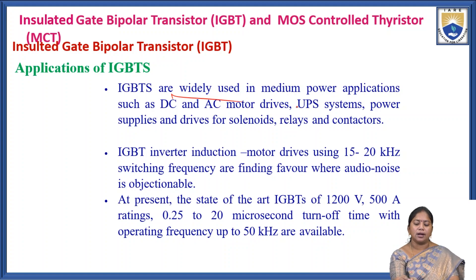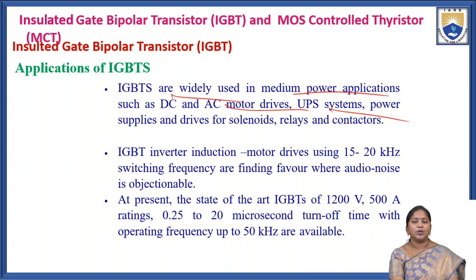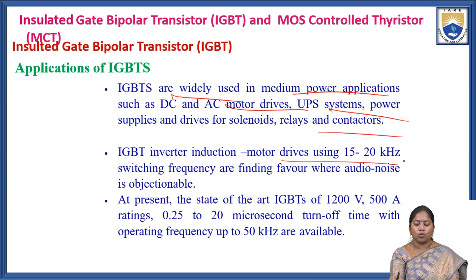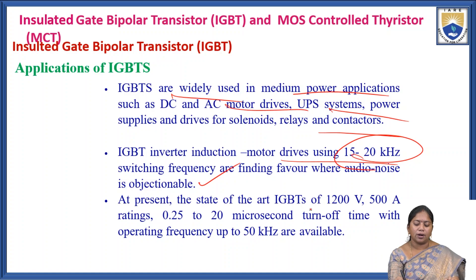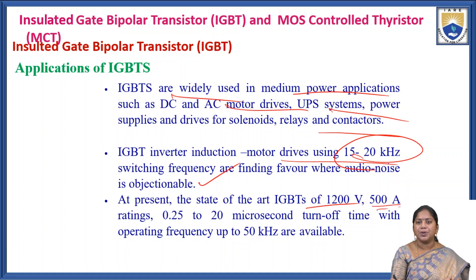IGBTs are widely used in medium power applications such as DC and AC motor drives, UPS systems, power supplies, and as drives for solenoids, relays, and contactors. IGBT inverters for induction motor drives use 15 to 20 kHz switching frequency where audio noise is objectionable. The state-of-the-art IGBT has ratings of 1200 volts and 500 amperes with turn-off times of 0.25 to 20 microseconds, and operating frequencies up to 50 kHz are available.